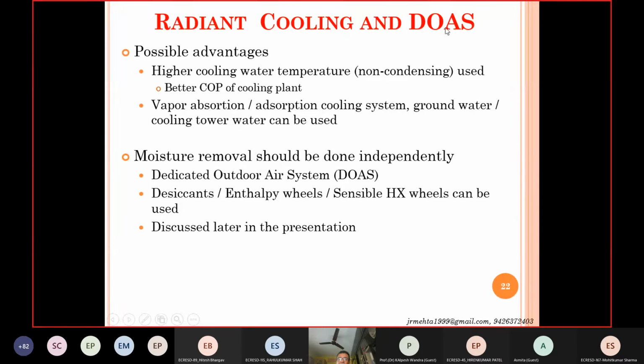So a unit which is dedicated for that purpose, supplying the outdoor air, is a dedicated outdoor air supply unit or system. Okay. So here the possible advantage is, this takes care of the latent load, because radiant cooling generally does not take care of the latent load. Combining these two could have advantages like higher cooling water temperature in the radiant cooling system used, so better COP of the water chilling plant. The higher temperature could be somewhere around 12 to 15 degree Celsius.